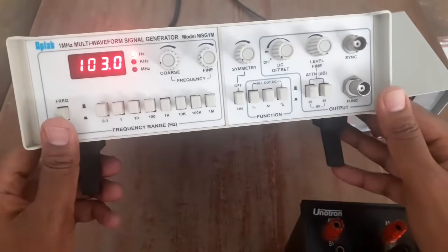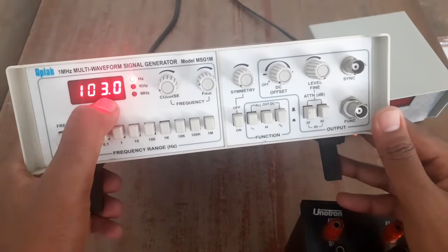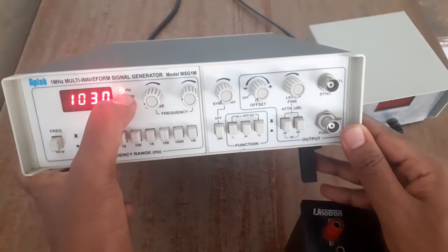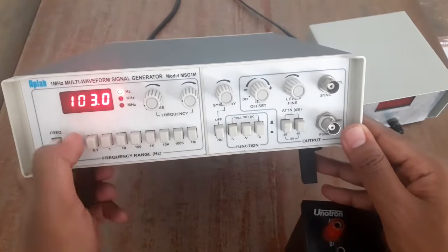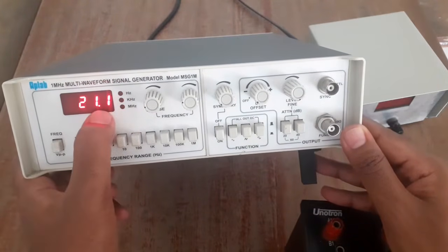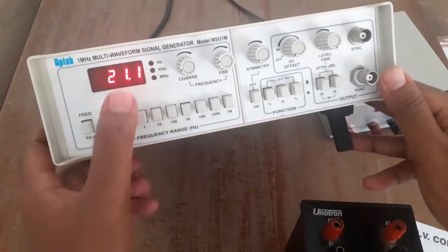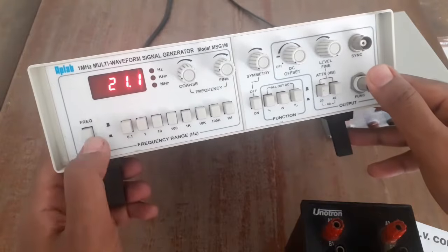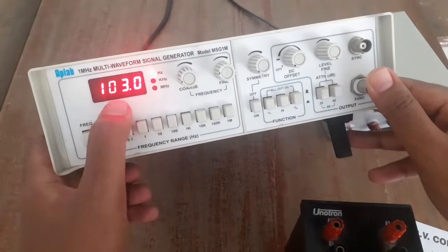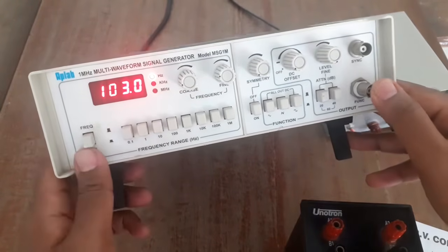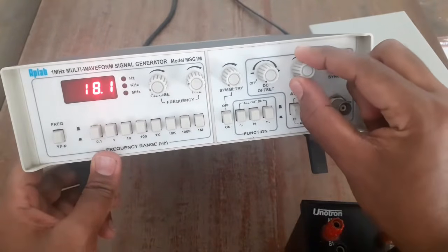And here this is a toggle switch to see the frequency and voltage of it. See, it is now showing frequency, and you can see here one more, it is showing Hertz, which means whatever the display is showing, it is in Hertz. So fine, now if I press this, it is going to show something else. If you press the button, it is going to show the output voltage which it is producing. If I remove this one, then it is going to show the frequency of it. So just to check.